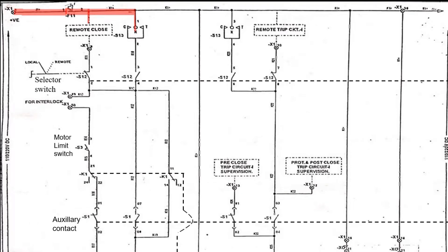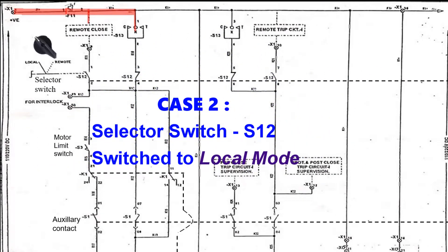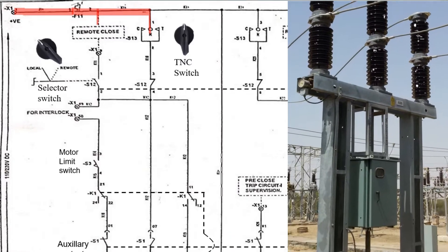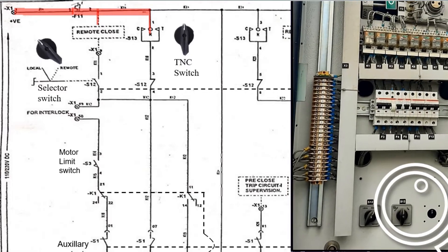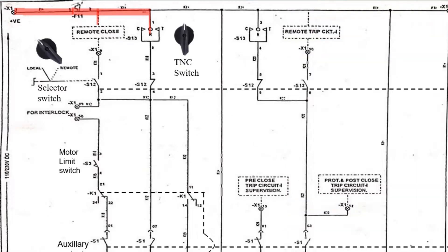Previously, we have seen that the selector switch S12 is connected in remote mode. Now let us consider case 2, where the selector switch is connected in local mode. Then the connection of S12 will be something like this. In local mode, the selector switch is connected to local and the operator performs the close operation where the circuit breaker is actually placed in the switchyard. Then the current will flow in this direction.